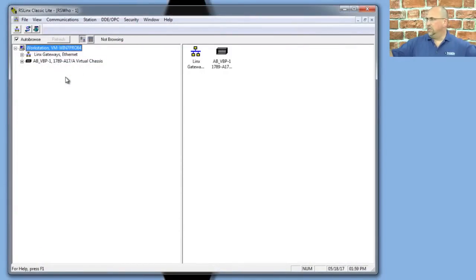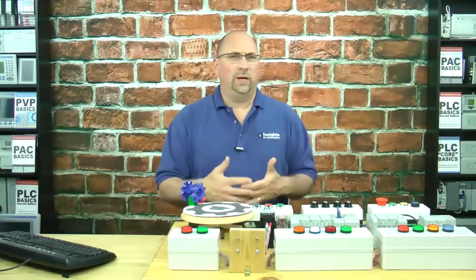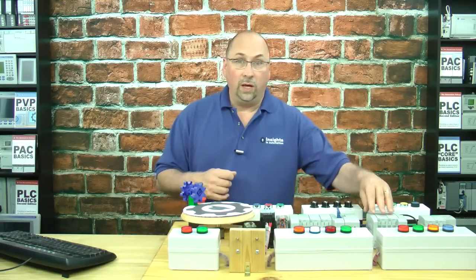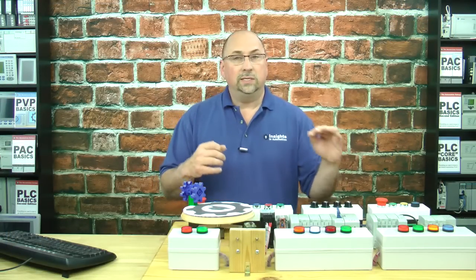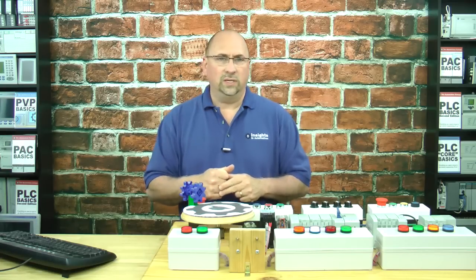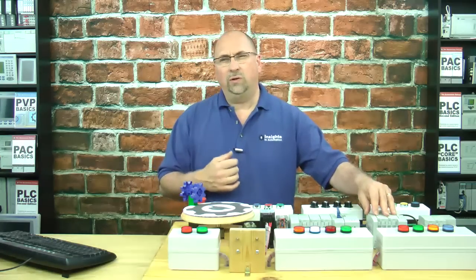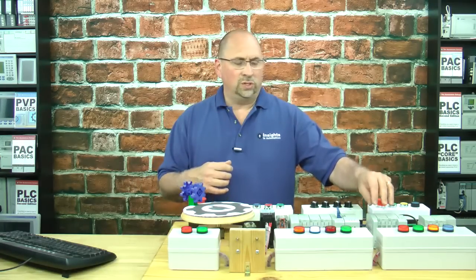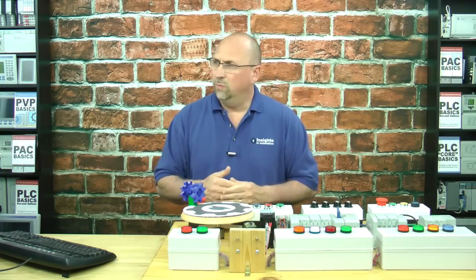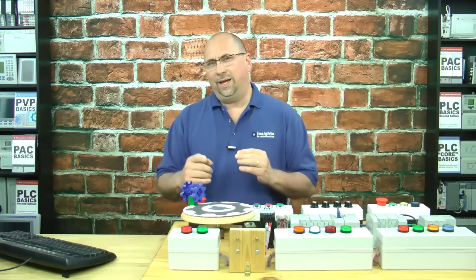And of course, when you unplug the Micro, you can see the USB driver disappears automatically as well. Another issue that can come up is if your Micro 800 is a newer firmware rev than your version of RSLinx — for instance, if your Micro 800 is version 10 but your version of RSLinx only knows about version 7 and below.